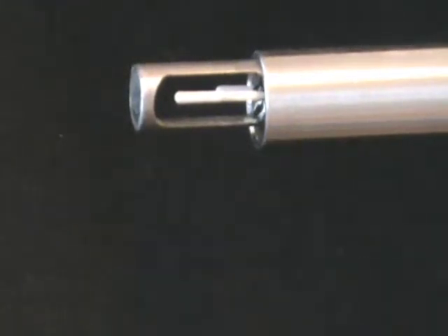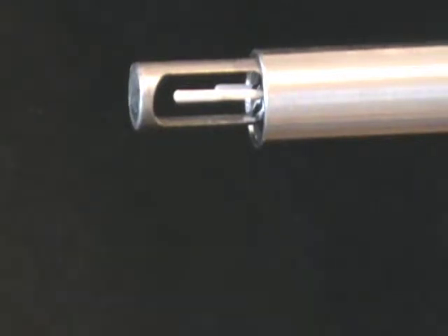So when wind blows across the wires, the anemometer has to put more current through the wires to keep them at the same temperature. It measures that difference in current and translates it into wind velocity. The faster the wind blows, the more the probe cools down, and the more current it has to put through.